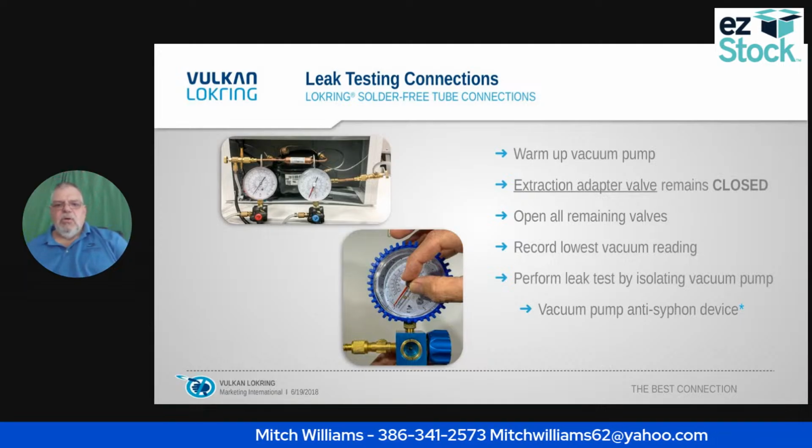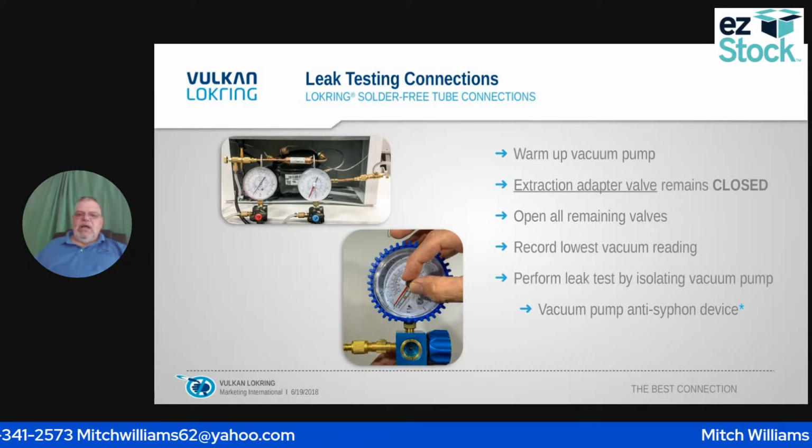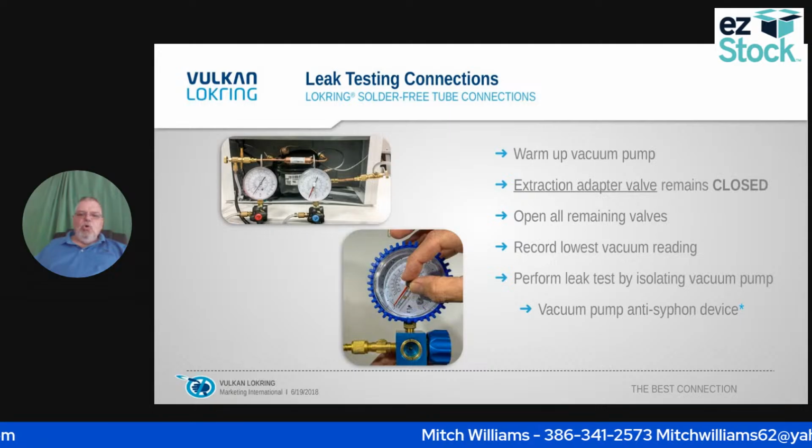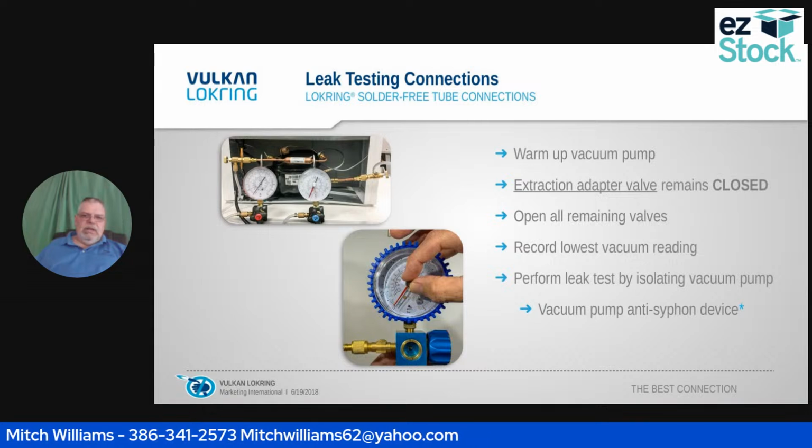Okay. So once I do all of this, I'm going to warm up my vacuum pump. I'm going to use the extraction adapter valve. It's going to remain closed. I'm going to open all the remaining valves. I'm going to record the lowest vacuum reading, which should be minus 29.